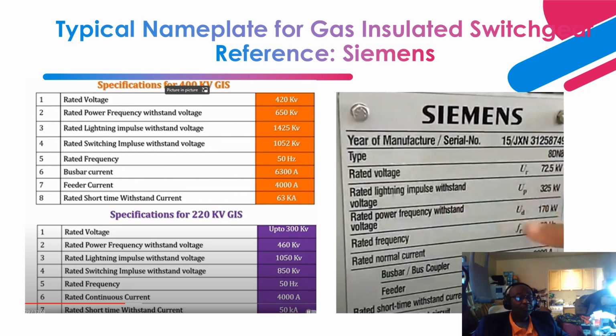The first thing is a GIS that is rated at 420 kV, right? So this is the maximum operating voltage, right? In achieving the maximum operating voltage, there is a factor of plus or minus 5%. So let's consider overvoltage, that is 5% above the nominal voltage of 400 kV. So your nominal voltage for this one is 400 kV, and 5% of that allows you to achieve 420 kV.